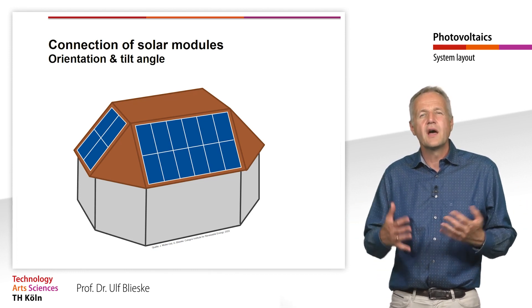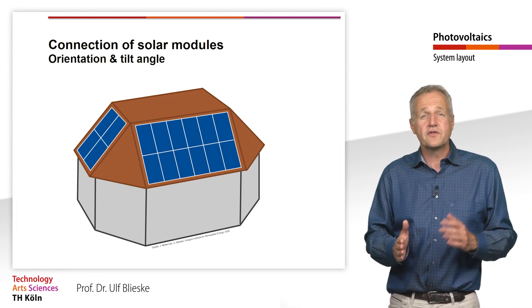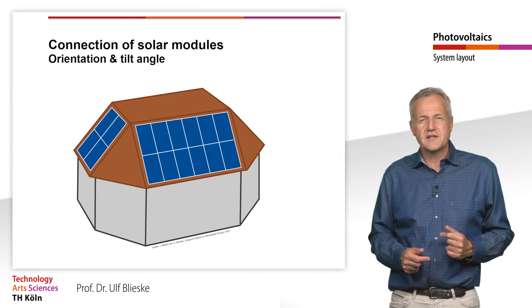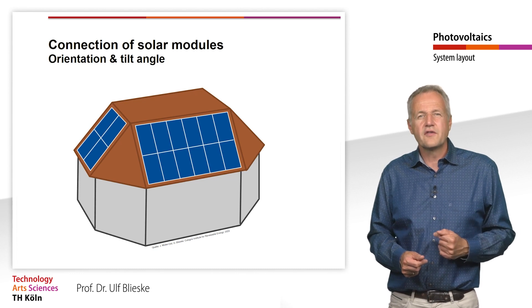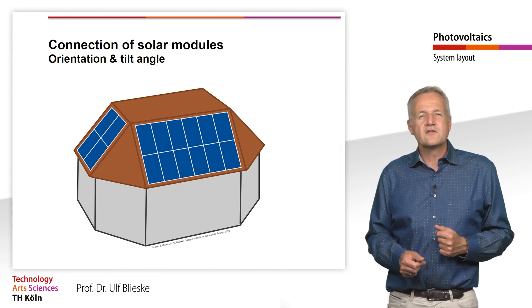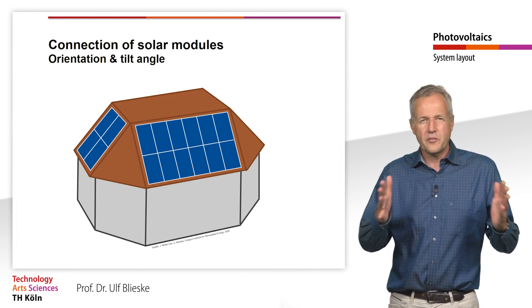As an example, let's look at a system in which differently oriented roof surfaces are covered with modules. Due to the different irradiation on the roof surface, the modules deliver a different current. To avoid power losses, the modules of the two roof surfaces should not be connected in a common string.